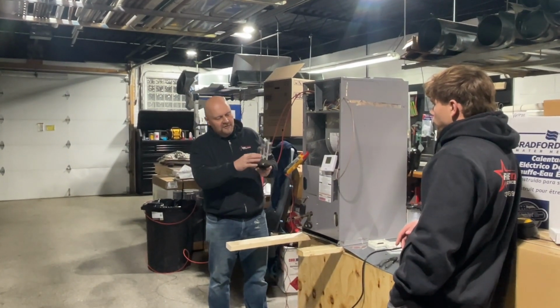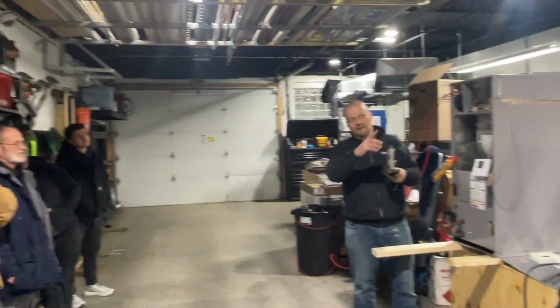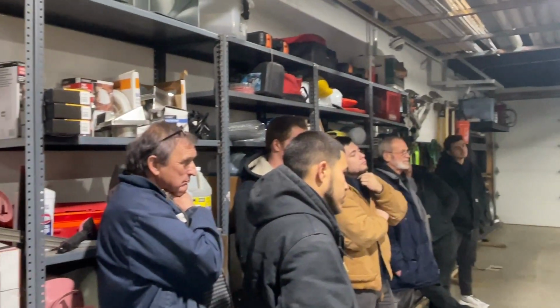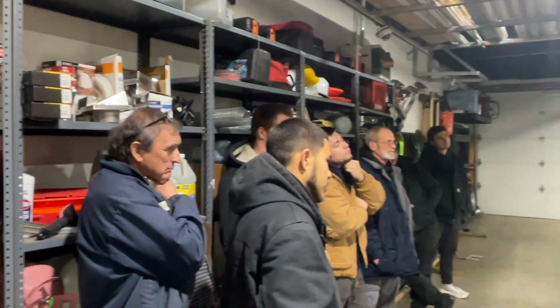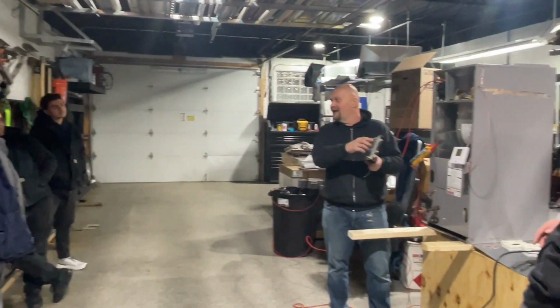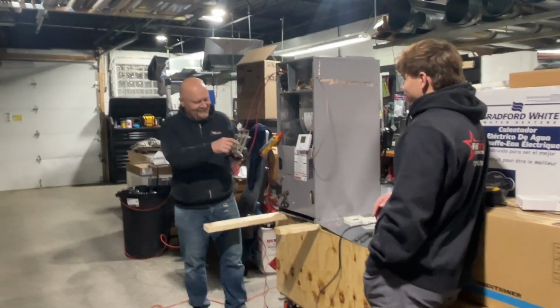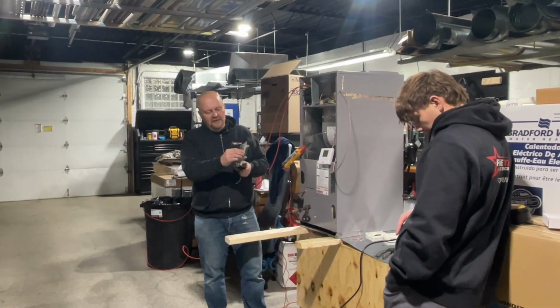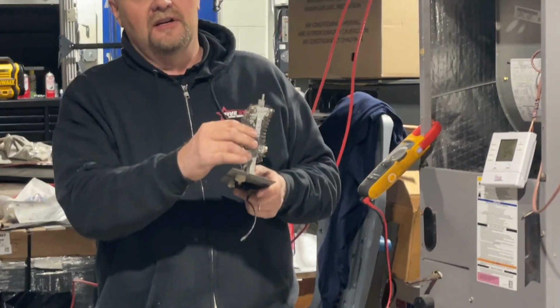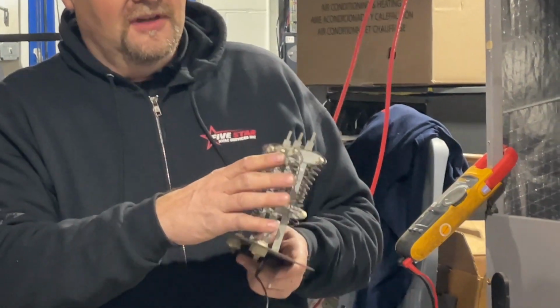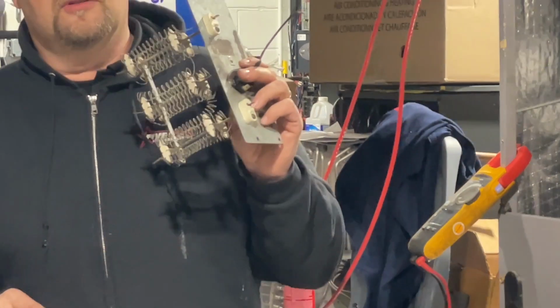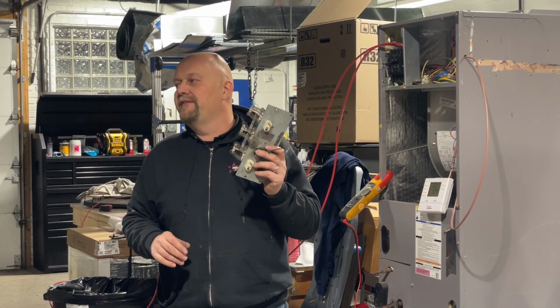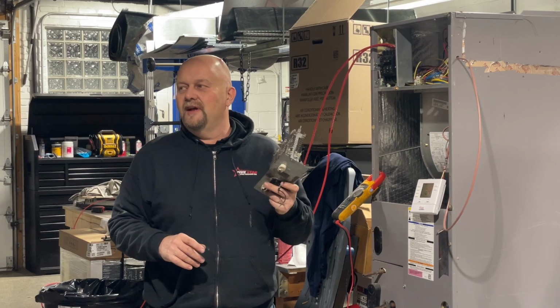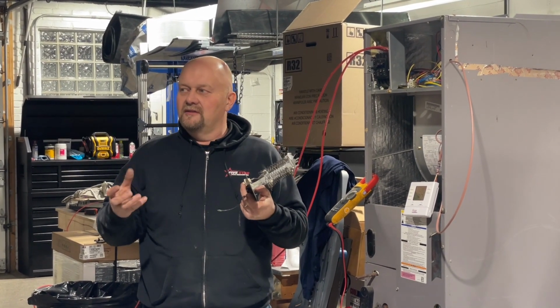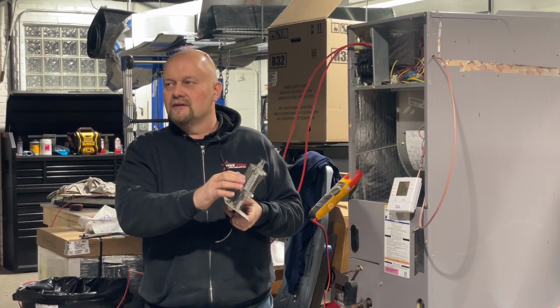So all that's going to happen is, you guys see this little wire, it's kind of like a radiant heating hose, right, where water flows through. All that happens is, instead of Mr. Aqua, it's Mr. Electron that runs through on both sides. Sergio loves that, Mr. Electron, Mr. Aqua. And what happens is, this wire heats up as it starts to conduct electricity. That's why it's conductive heating, right? It starts to heat up to a point where normally you're going to see this turn orange or red unless the fan is running. Even sometimes with the fan running, if you could still see it, sometimes you can through like a humidifier pad, you're going to see center orange, right?